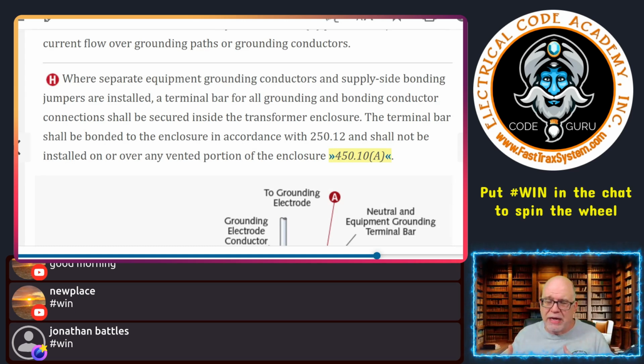And so we need to make sure that they're vented, okay? That type of thing. So we don't want to obscure any of the venting, okay? So there may be already one installed down there for you. It may be that you have to drill holes and follow the requirements for mounting it in 250.8, follow the rules in 250.12, and add your own. But most of the transformers that I run into, they put a bus down there already. And if it's already manufacturer installed, then I'm gonna use it. That's what I'm gonna use.